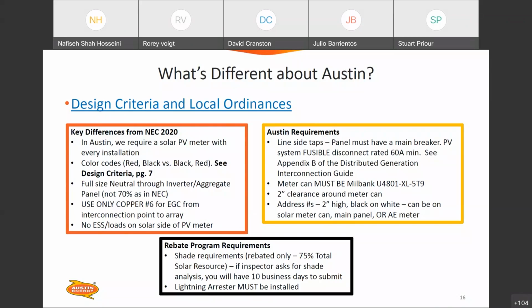Something else we don't allow is having any energy storage or customer loads on the solar side of the solar meter. The quickest way to verify this is that everything coming off the roof goes through the solar meter first, then you can distribute the loads however needed. But you can't have loads or a reverse load on the solar meter—it can only flow one way.